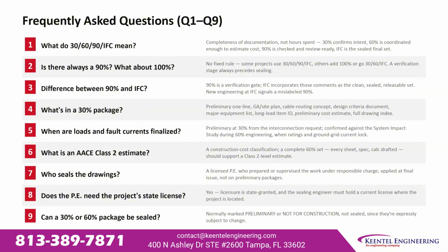What is in a 30% package? Preliminary one-line, general arrangement and site plan, cable routing concept, design criteria document, major equipment list, long lead item identification, preliminary cost estimate, and a full drawing index. When are loads and fault currents finalized? Preliminary values are set at 30% from the interconnection request. They are confirmed against the system impact study during 60% engineering, when equipment ratings and grounding grid fault current lock in.